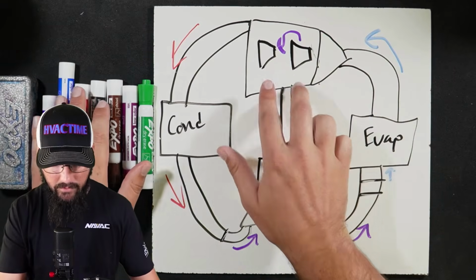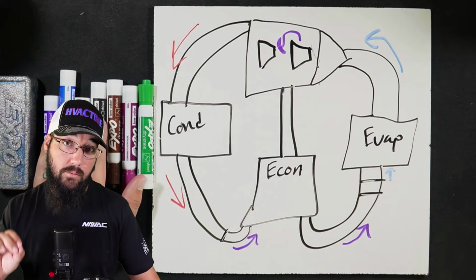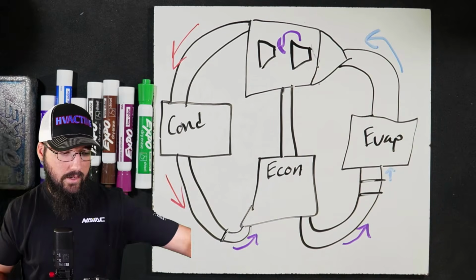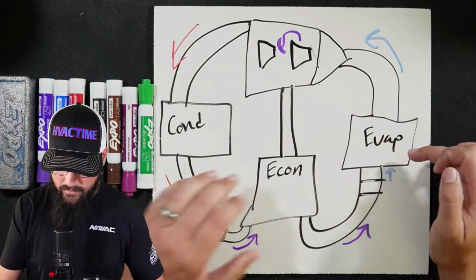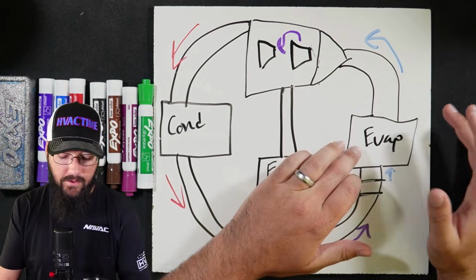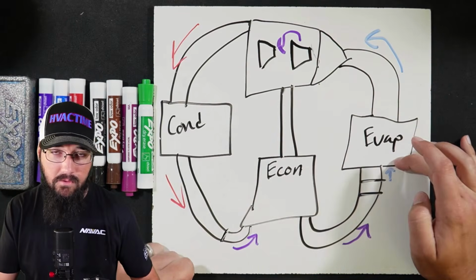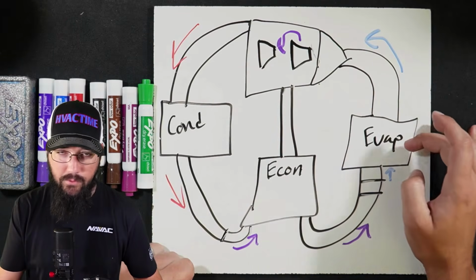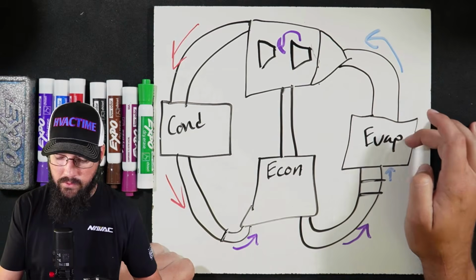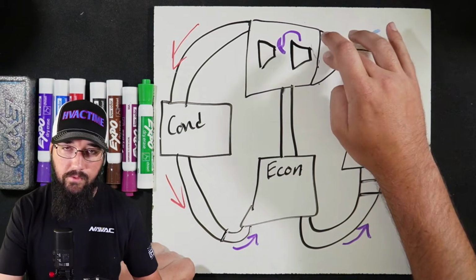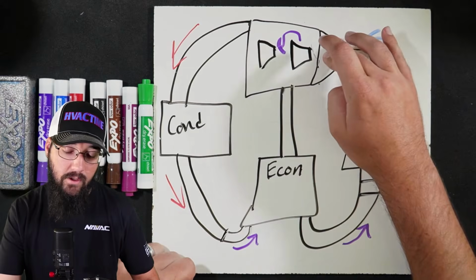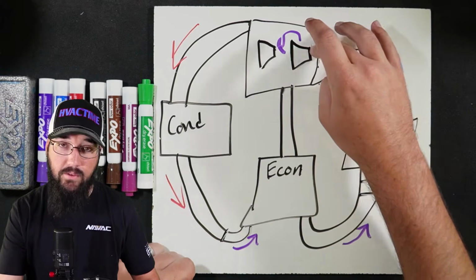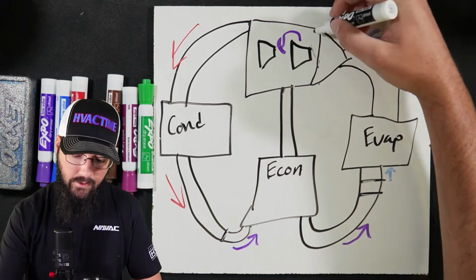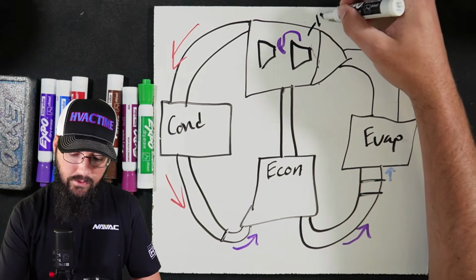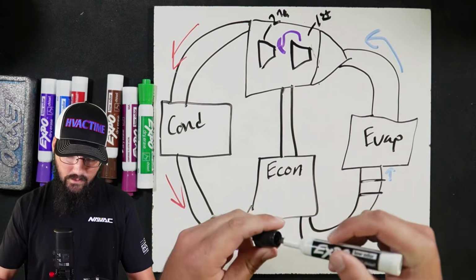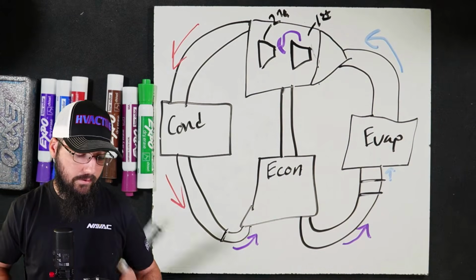Now this specifically has 2 impellers, so this is going to be our F series in this lineup. What's happening here? The evaporator is going to function the same. This is a flooded style of evaporator. Refrigerant's going to sit over the tubes. It's going to boil off. Vapor, superheated vapor comes back into the first stage impeller. This is going to be first and then second. So it's a multi-stage design compressor on these.